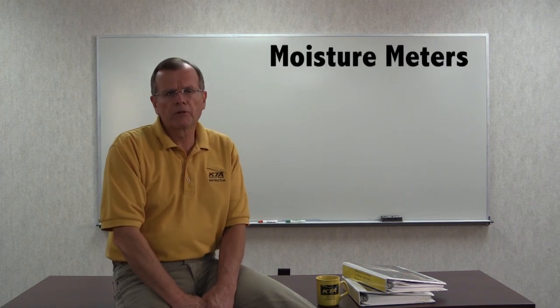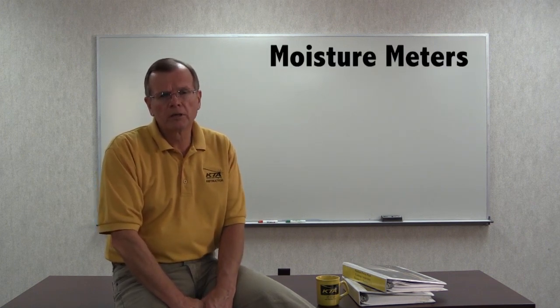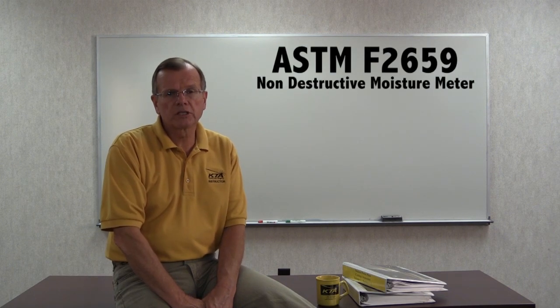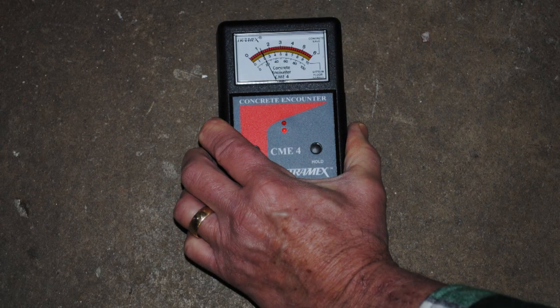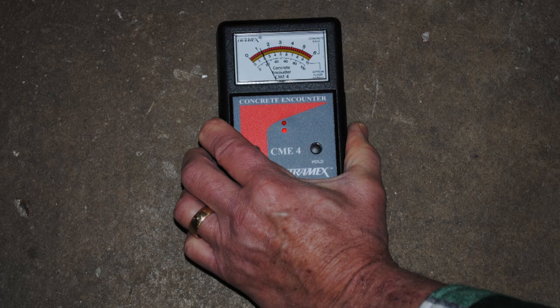Moisture meters. There are a number of them. One is electrical impedance. The use of this meter is addressed in ASTM F-2659. This is a non-destructive comparative test involving the use of an electronic moisture meter. It is used to measure the electrical impedance of the floor beneath the instrument. This method provides a quick way to obtain an approximation of the relative moisture content of the concrete.